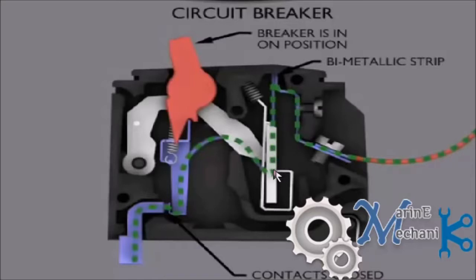As the current flows, the bimetallic strip gets heated up. Let's say the circuit breaker is rated for 20 amps. Till 20 amps nothing will happen to the bimetallic strip. Of course it will expand, but the expansion will be within the limit, it will not trip the operating links.